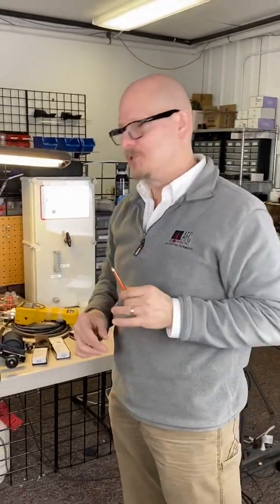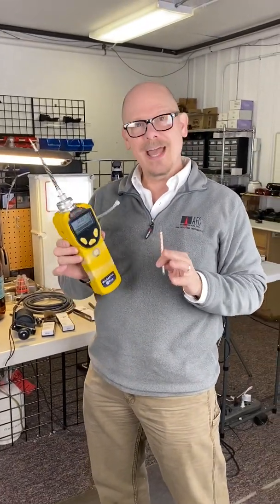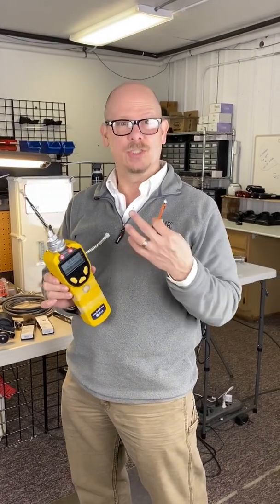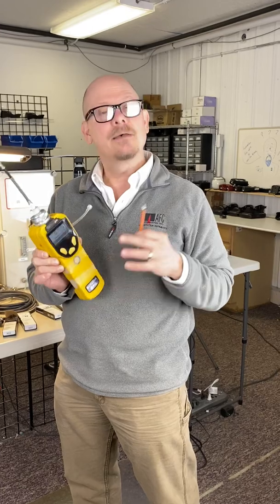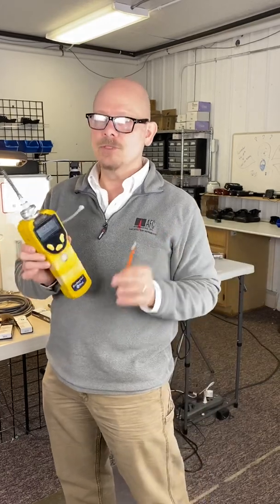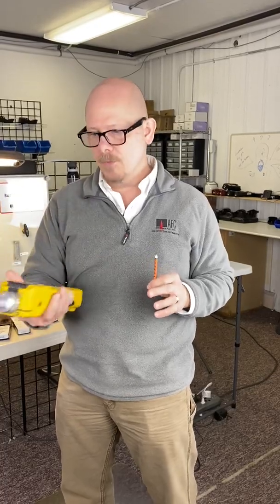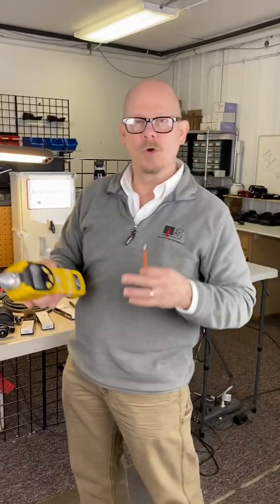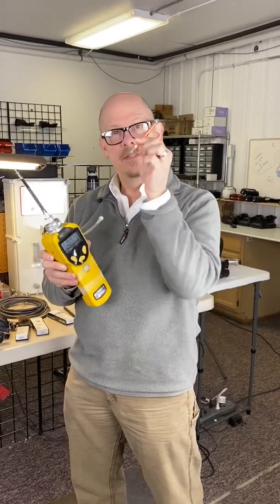One interesting thing about this particular tube: if I were to use a PID and I'm looking for methanol, PIDs use lamp energies to actually detect the presence of a gas. 10.6 electron-volt lamps used in most PIDs don't have enough energy to see methanol. They do see ethanol and isopropyl alcohol, but when we get into methanol, the PID is blind to it. So you may walk around with a PID such as this MiniRAE 3000 and get no hits in the presence of something that's actually there. In the case of hazmat or a plant, you want to know what you have, so detector tubes come in handy.